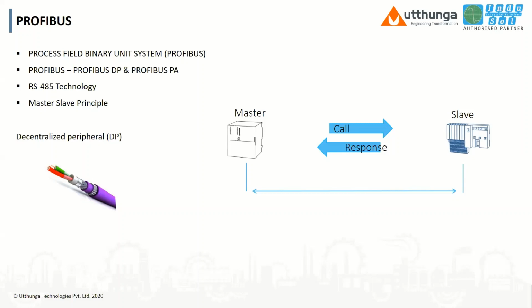So Profibus is Process Field Bus. This is one of the protocols that is used in industrial automation. We have different industrial automation protocols such as HART, wireless HART, Profibus, Profinet, Foundation Fieldbus, ISA 100 technologies. In adopting these technologies, Profibus also has a major footprint in the industry. Now, Profibus itself has two types, Profibus DP and Profibus PA. Profibus DP stands for Decentralized Peripheral, and Profibus PA is for Process Automation.